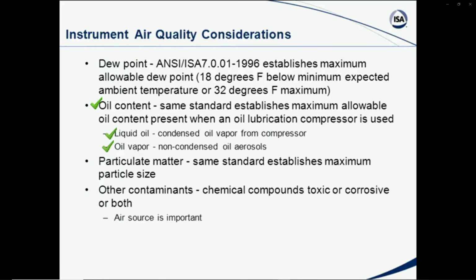But in the instrument air, we don't want to have that, as well as we do not want to have large particulate matter, which will plug up the flapper nozzle areas that we're working with. And also we need to look at other contaminants, and in general, the air source is important and is a consideration on projects or any type of installation, industrial chemical plants, pulp paper mills, power plants, things along that line. So we need to be aware of that, and you need to be aware of the standard and the fact that there is a particular concern about instrument air quality.